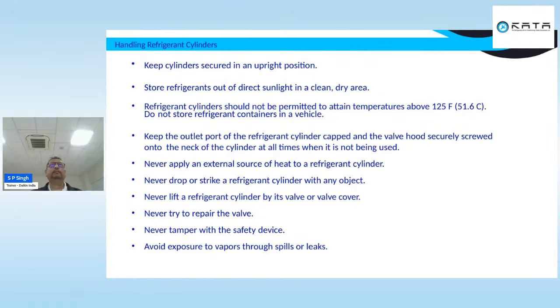Here you can see some cylinders, and how to secure the cylinder in an upright position. In maximum cases we find that cylinders are kept lying down. They should be kept in an upright direction, and the refrigerant temperature should be around 50 degrees or less than 50 degrees.